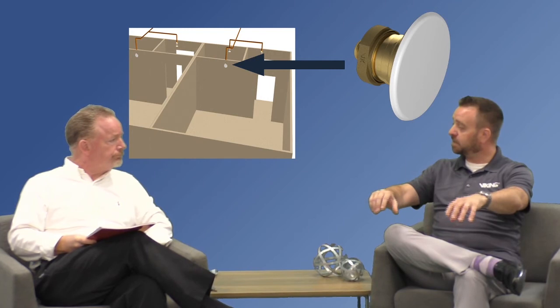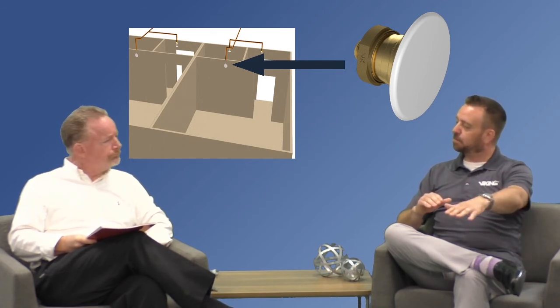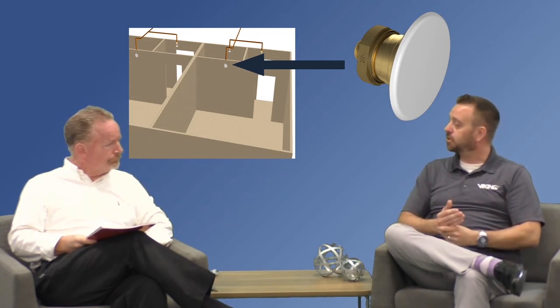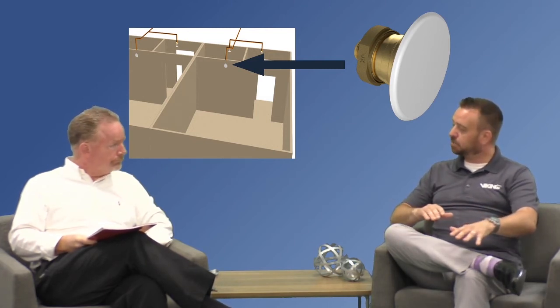So in the entryway and the bathroom, if you went with, say, a 3.0 K factor pendant sprinkler, because you're not covering a large area, it helps you to reduce the overall flow of your calculations based upon the pressure that's going to be required out of that sidewall that's protecting a much larger area. So that's another reason why we offer so many different K factors, as you can utilize the different sizes to be able to get the best hydraulic calculations you can for your system.